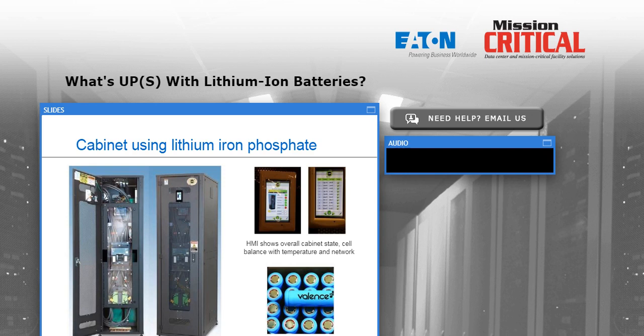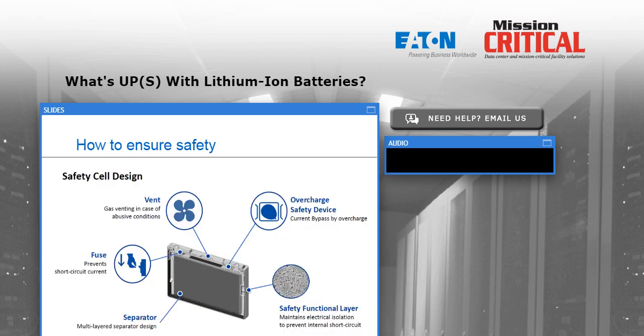and 20 of these batteries in a cabinet gives us the 480 volts DC that we need to support a UPS system or a typical large UPS system. And again, these batteries, like all lithium batteries, it depends heavily on how they're manufactured, but this is a very commonly used and recognized as a safe type of packaging for the lithium chemistry. This is the lithium iron phosphate solution.